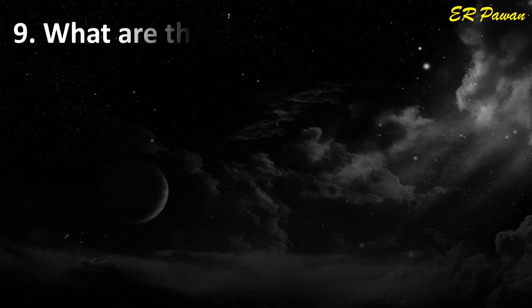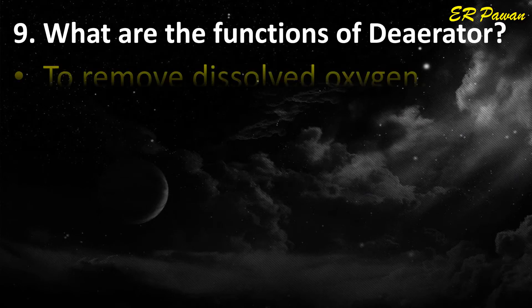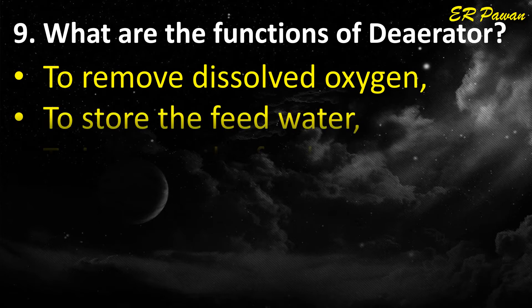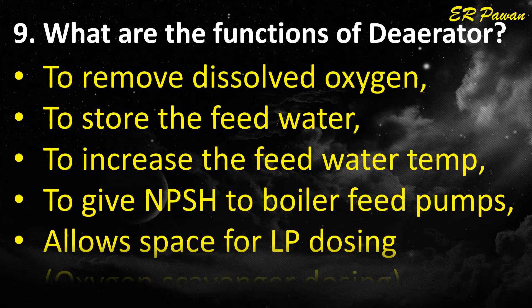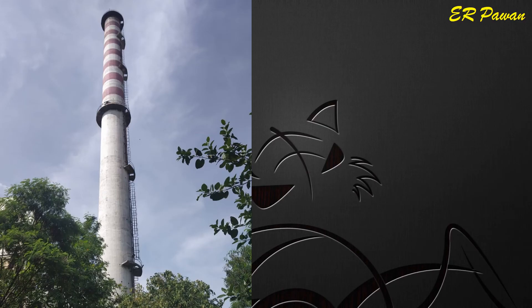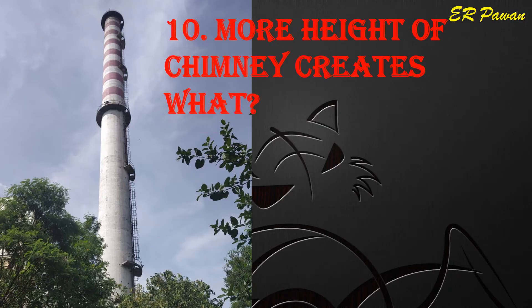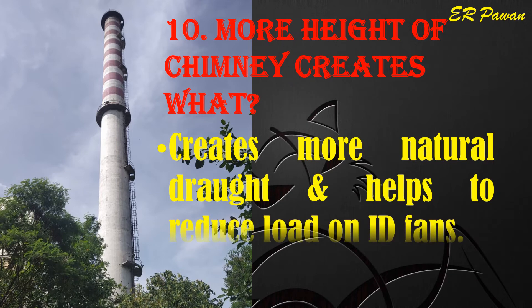Question 9: What are the functions of a deaerator? To remove dissolved oxygen, to store the feed water, to increase the feed water temperature, to give NPSH (net positive suction head) to boiler feed pumps, and to allow space for LP dosing and oxygen scavenger dosing. Question 10: More height of chimney creates what? It creates more natural draft and helps to reduce load on ID fans.